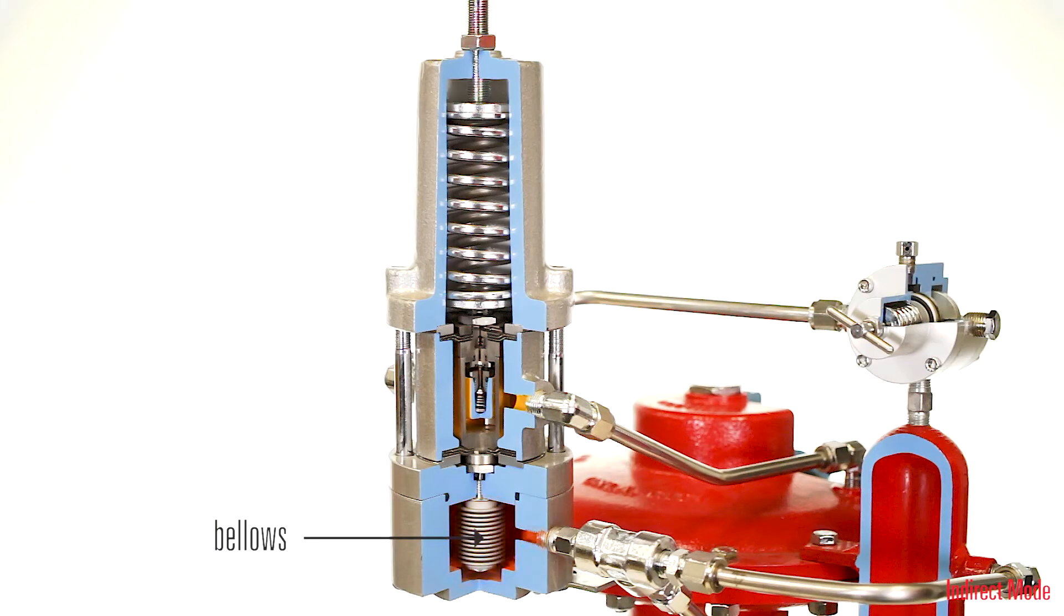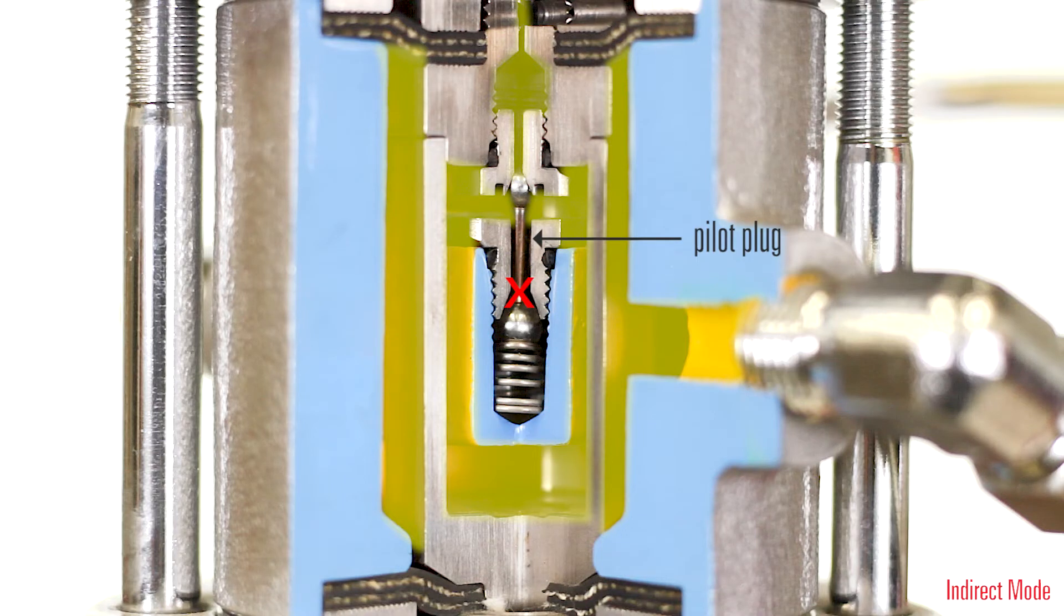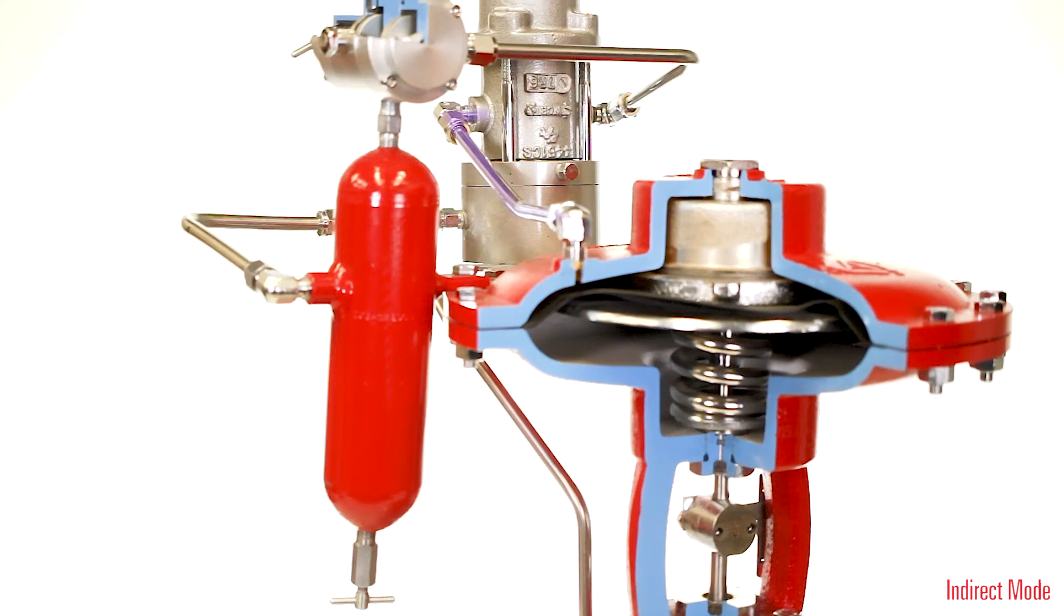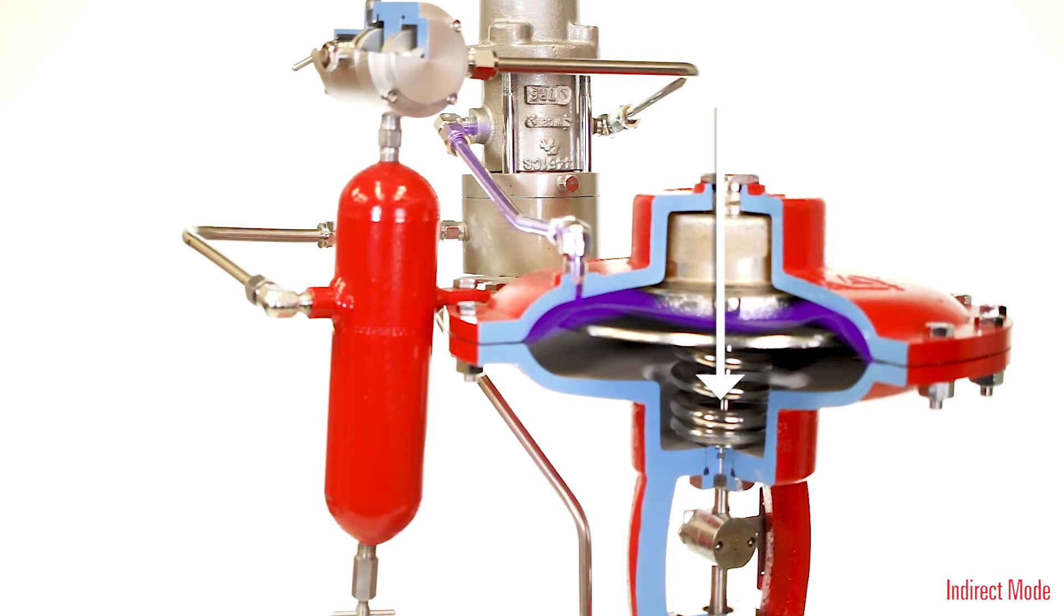A decrease in sense pressure allows the spring to push down on the bellows, which repositions the pilot plug assembly, closing the vent port and opening the supply port to output. This will position the valve toward close.